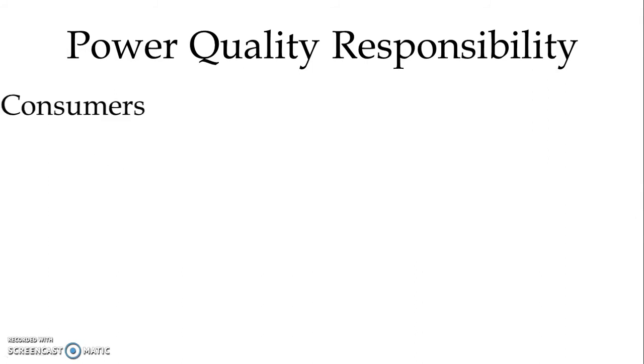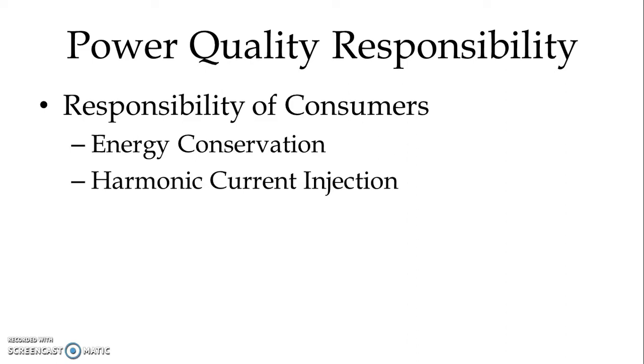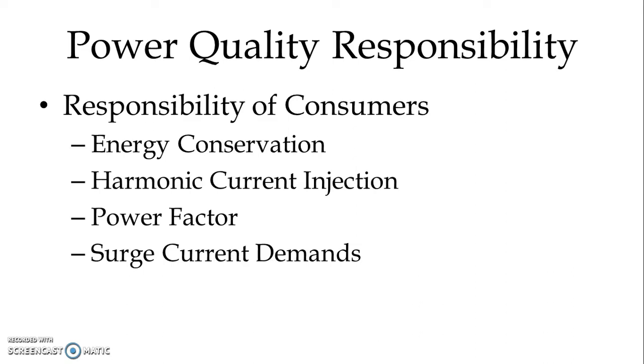Then we have power quality responsibility from the consumer end. Energy conservation is one very important concept and consumers must learn to optimize energy. Then harmonic current injection — because of load conditions we now have a number of electronic loads, and because of this, harmonics are generated and injected into the power lines. Up to a certain limit, harmonic current injection is allowed, but beyond that it must be restricted. Power factor is again one very important factor which can be controlled from the consumer end, as well as surge current demands. If power suppliers and users each do their part, power quality is improved and power consumption is optimized.